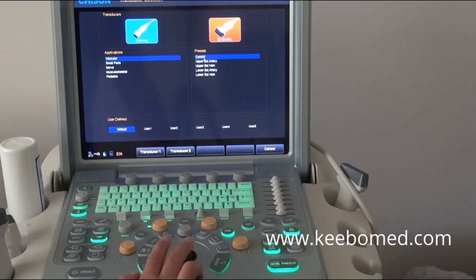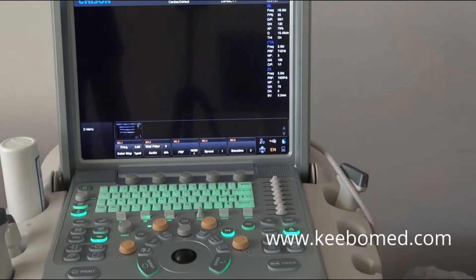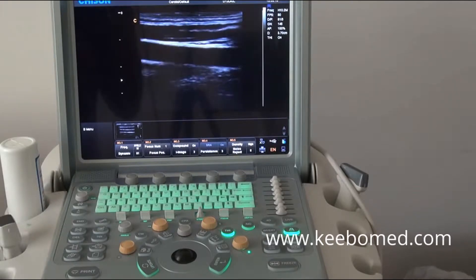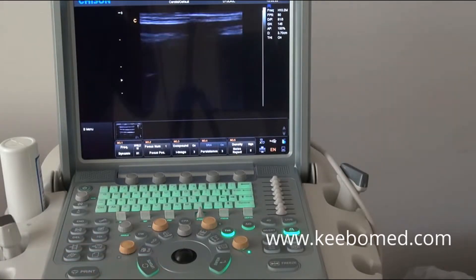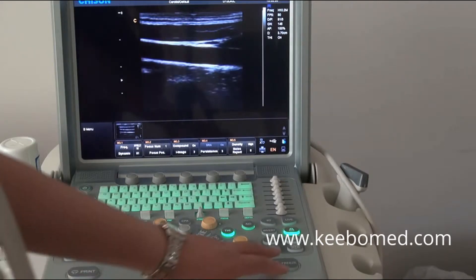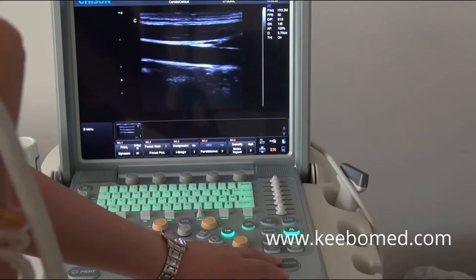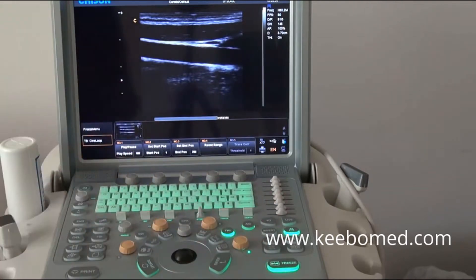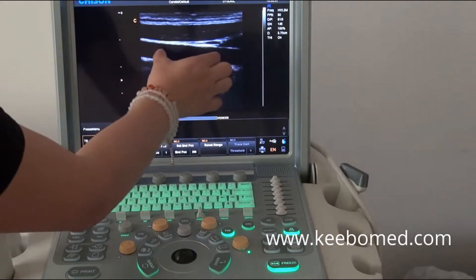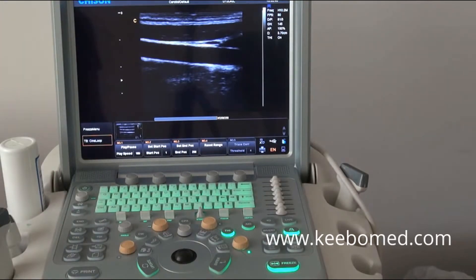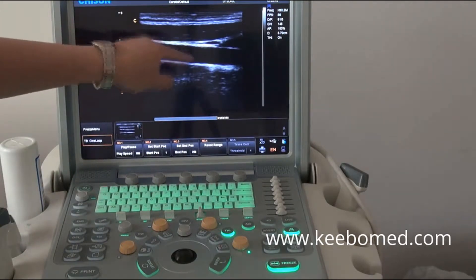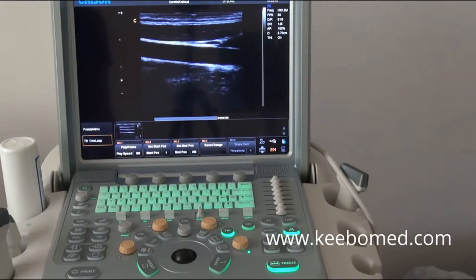Choose the vascular application and go into B mode. For this image, you can find that inside the vessel is very clean with no noise. Not only the posterior intima can be displayed continuously, but also the anterior intima can be displayed well. And in the near field, different tissue layers can be displayed well.